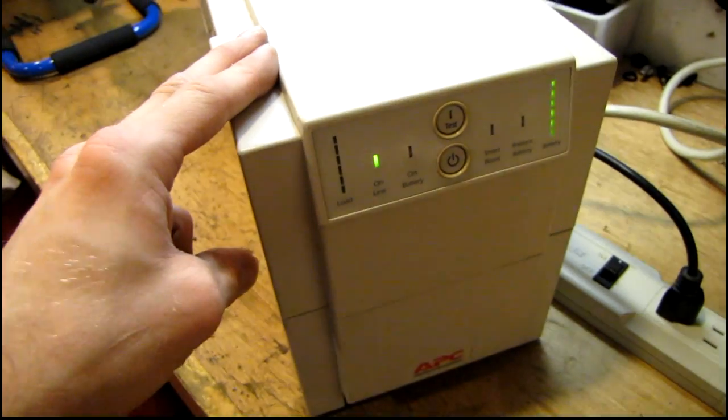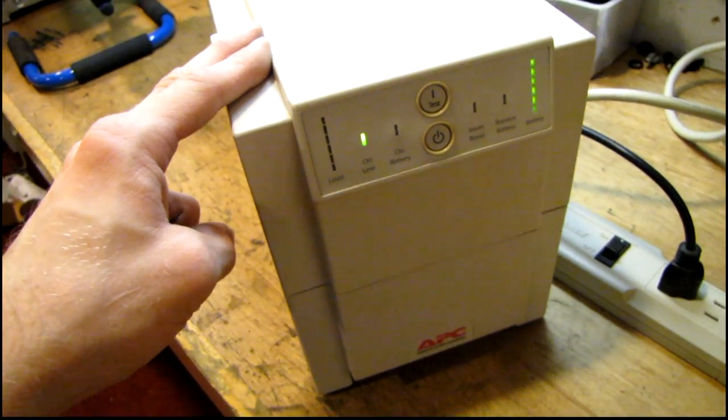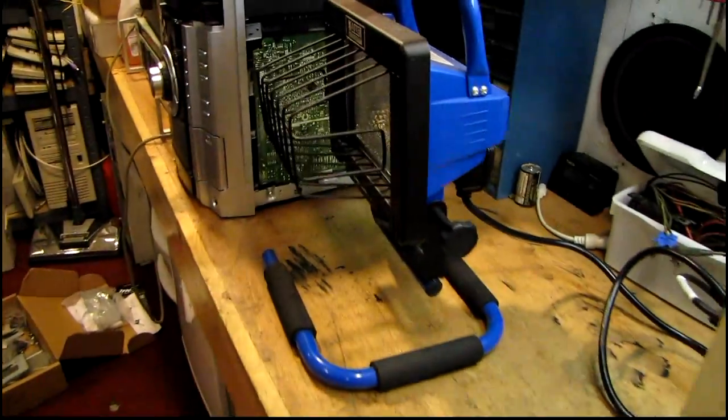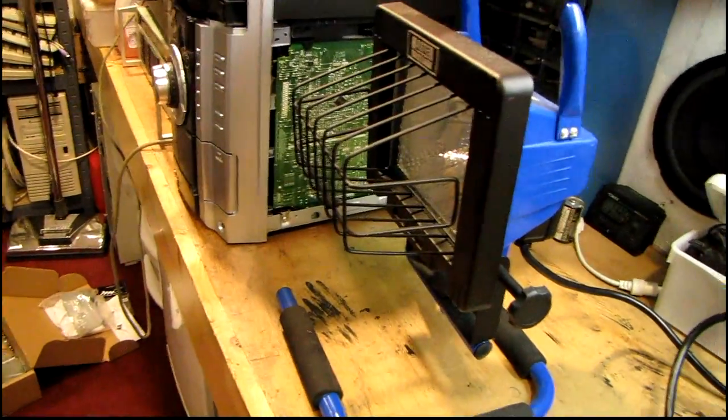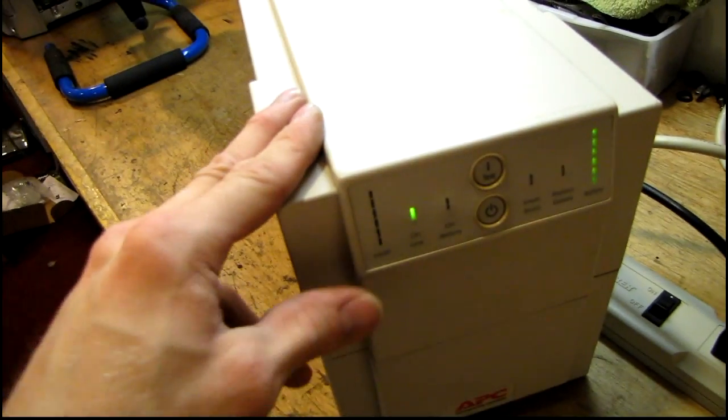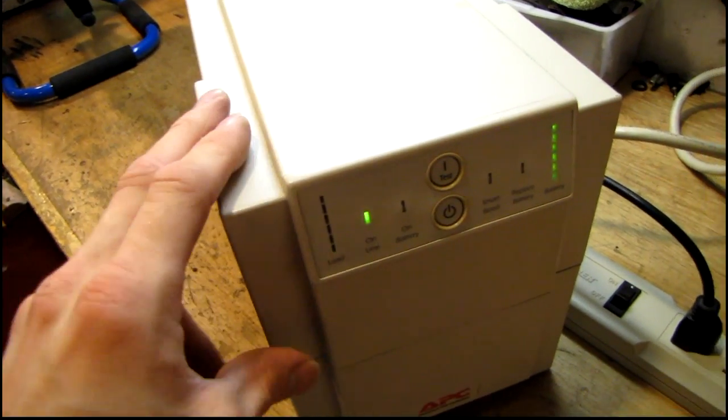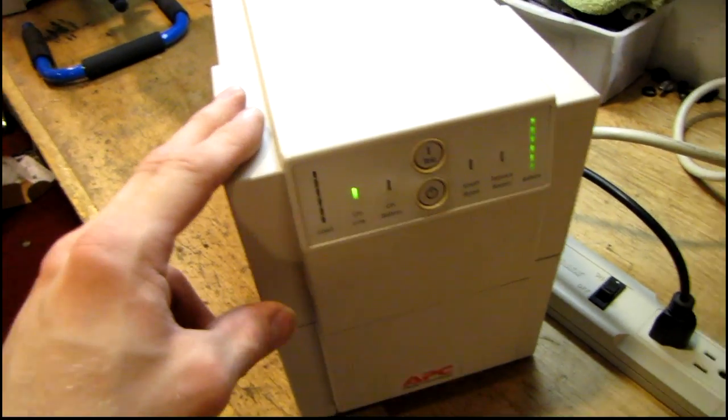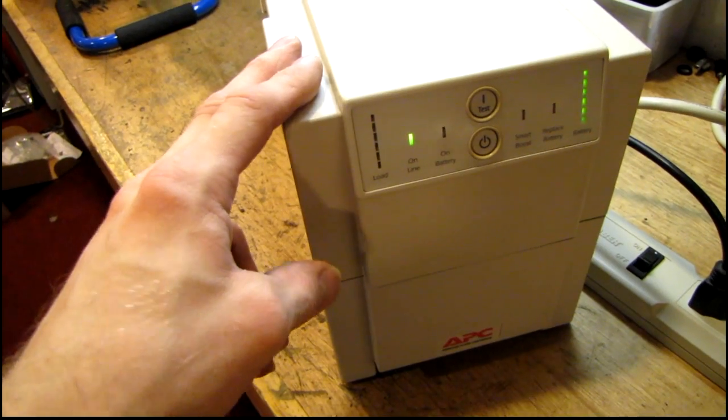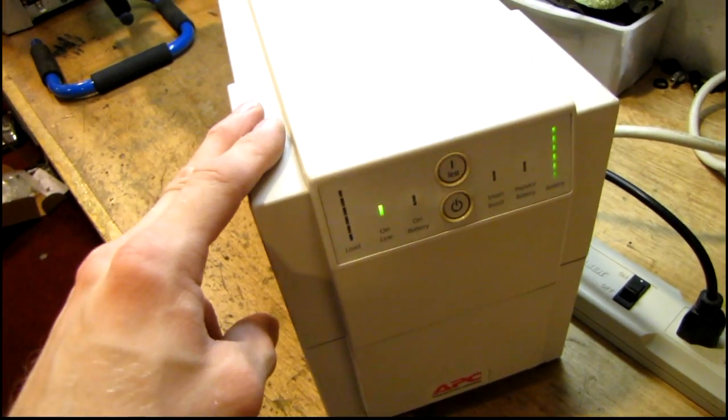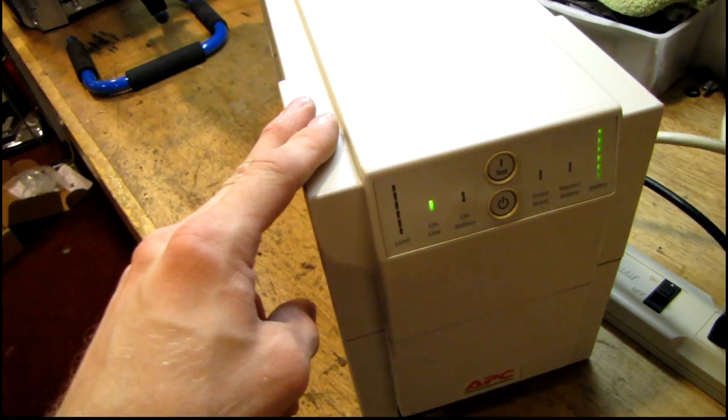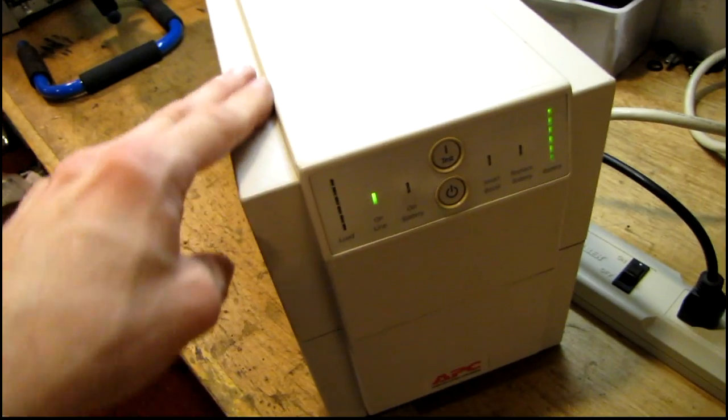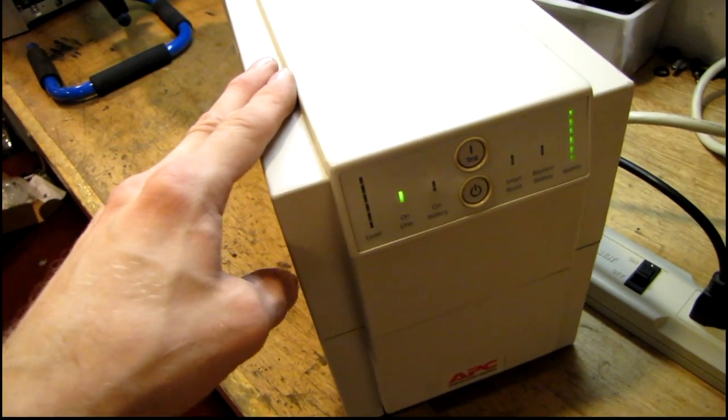And it has to be approximately 50% of the capacity that the UPS has. Since this UPS can put out 900 watts or 1250 volt amps, I'm going to use a 500 watt halogen work light. That's approximately 50 or 60% load capacity on this.